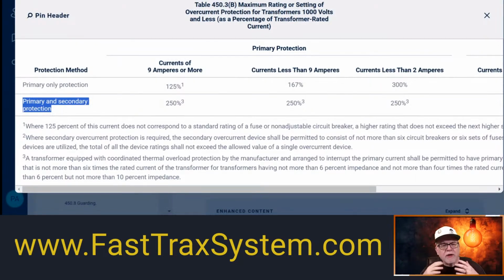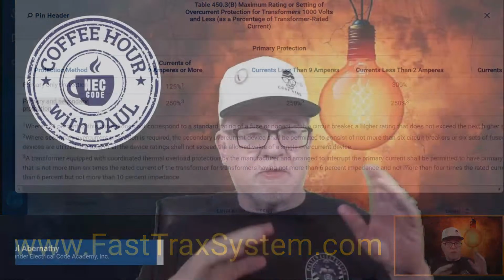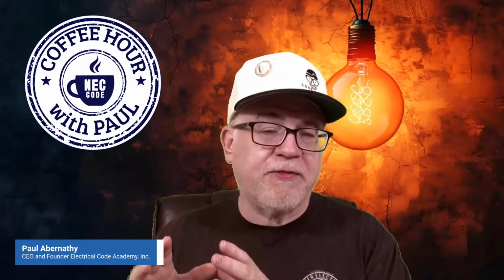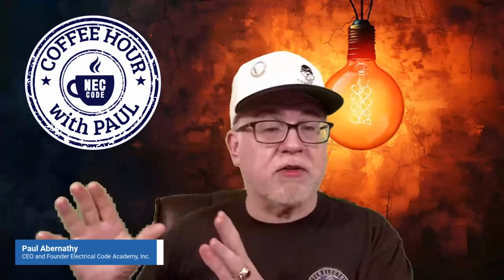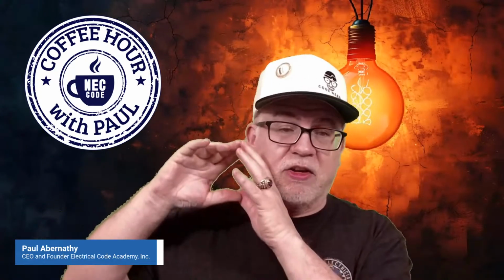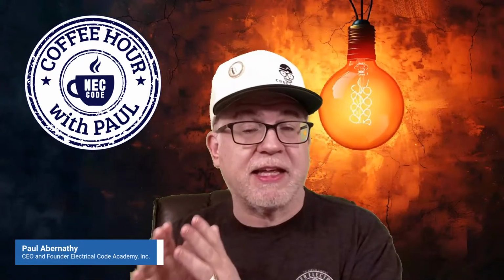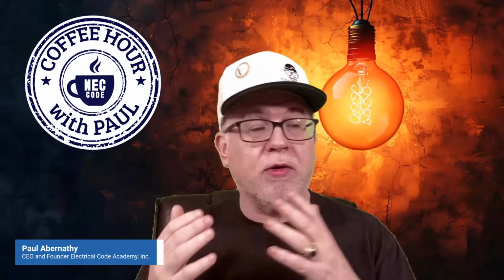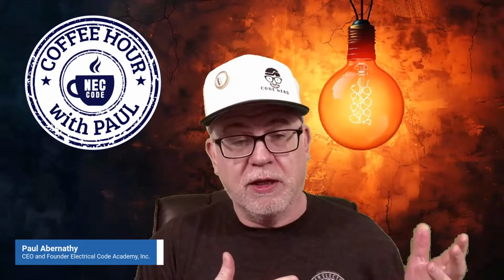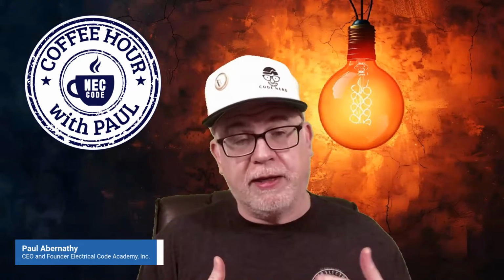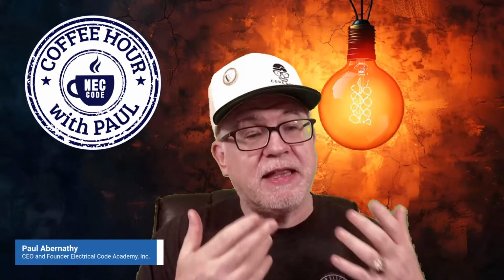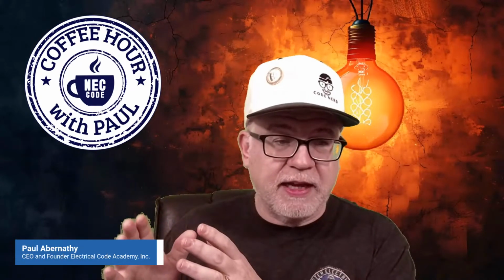Now, here's an important distinction that I want to get out of the way because people get confused on this. These are two different rules. Okay, the 450s are talking about the transformer. We're talking about protecting the transformer. Could it be that that transformer protection also is going to protect the conductors? Absolutely. But where are the conductor rules? Well, the conductor rules are in 240. Okay, 240.4, their protection. So we still have to meet them. There's nothing here that can circumvent that.